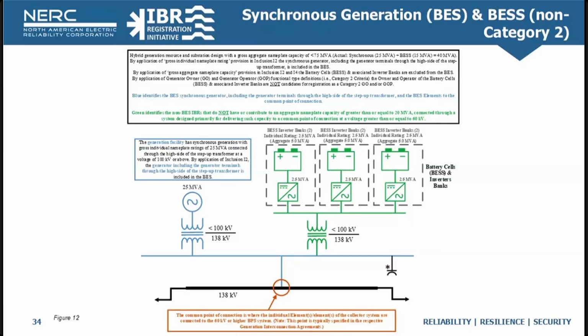Again, the first step is to apply the BES definition to the facilities. So by application of inclusion I2, the 25 MVA synchronous generator with a connection at a voltage of 138 kV is included in the bulk electric system. By application of the aggregate nameplate capacity provision of greater than 75, which is part of inclusion I2 and inclusion I4, the 15 MVA battery energy storage component is excluded from the BES. And this is based on the facility aggregate nameplate rating being 40 MVA, which is below the 75 MVA threshold.